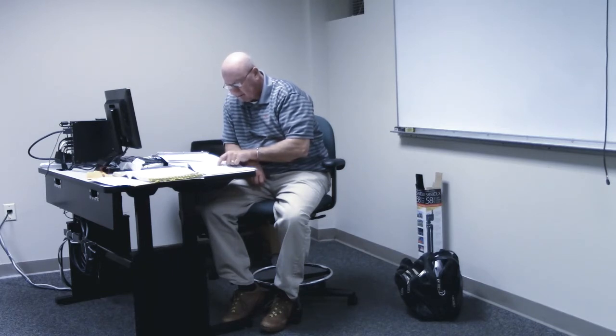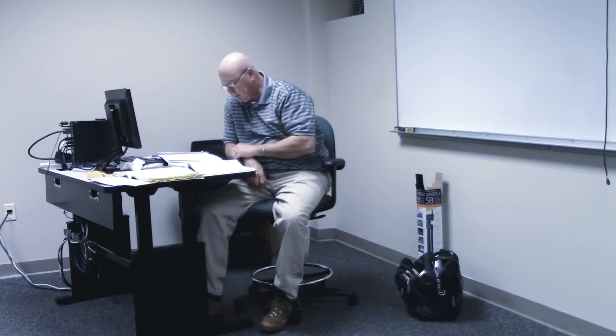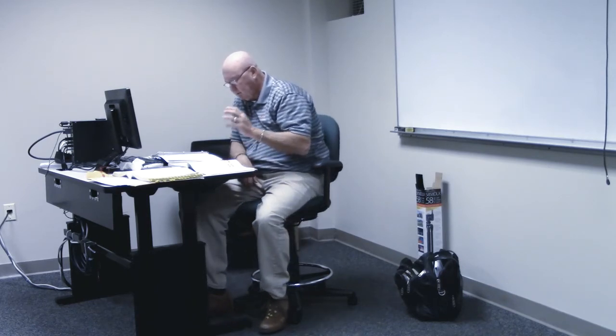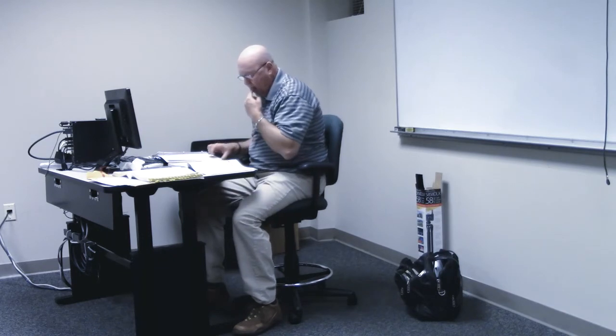The life safety branch supplies power to these items needed to ensure the safety of the building, so it may include exit signs, stairway lighting, alarm system, communication system. So that's under one of our red areas, isn't it? Whereas the critical branch supplies power to areas that are directly related to patient care. These include pharmacies, emergency rooms, intensive care units, and so on and so forth. So I just kind of know that whole paragraph, understanding the difference between equipment branch, critical branch, and life safety.